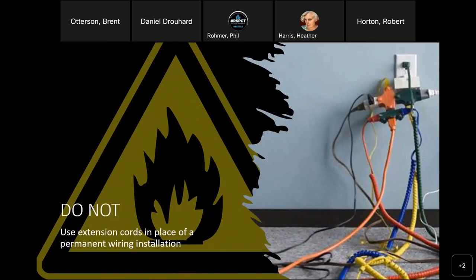Here's another example of what definitely not to do: do not use extension cords in place of permanent wiring. This person may have been creating a home office, maybe during COVID, but remember, extension cords are not permitted for wiring. The conductors are too small, and they're not approved for continuous use. Look at how one outlet is powering all the devices plugged in—every one of those connections is a potential cause of an electrical fire, because each connection creates electrical resistance. Resistance causes heat, heat causes fires.